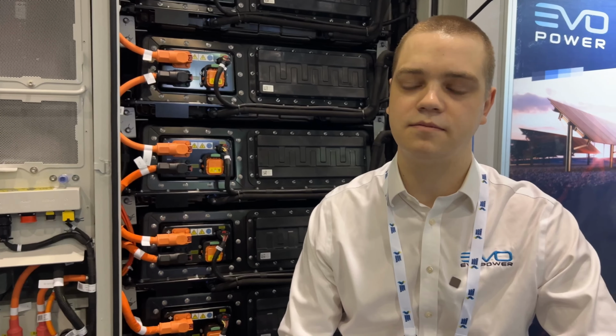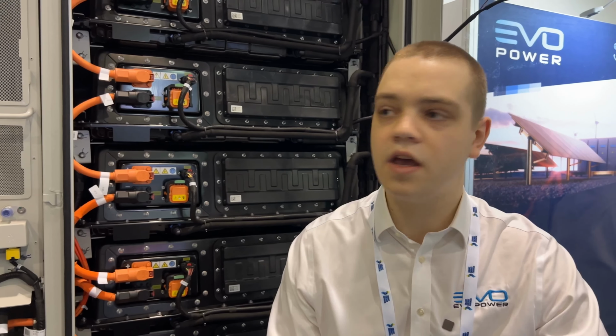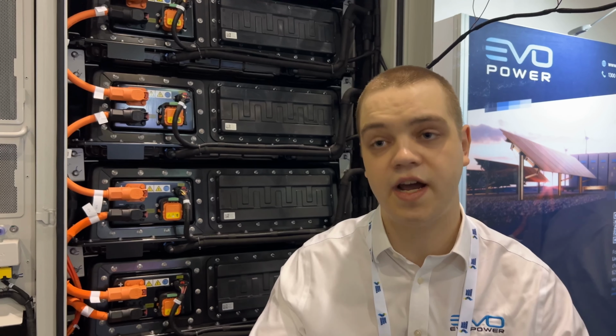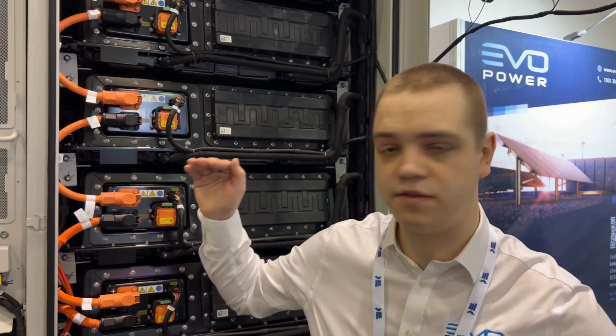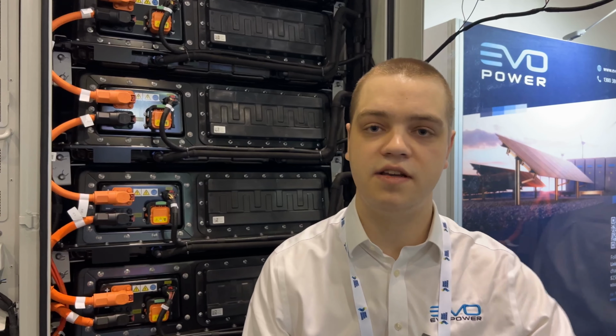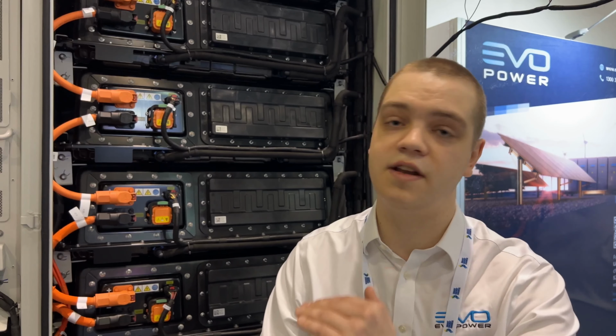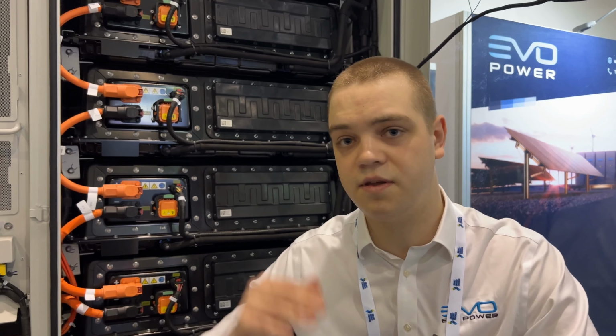These are series connected - what voltage ranges can you use? For the Neo system, we use between 800 to 1200 volts, which is 6 of the modules, and for some DC coupled and amp series systems, we use 7 and 8 modules. At those voltages, what's the PCS going to be? The PCS for the Neo system will be a Delta PCS 100 HV, ranging from 800 to 1200 volts. We're also using some Ingeteam PCSs for much higher, up to 11 kV transformer kind of systems.